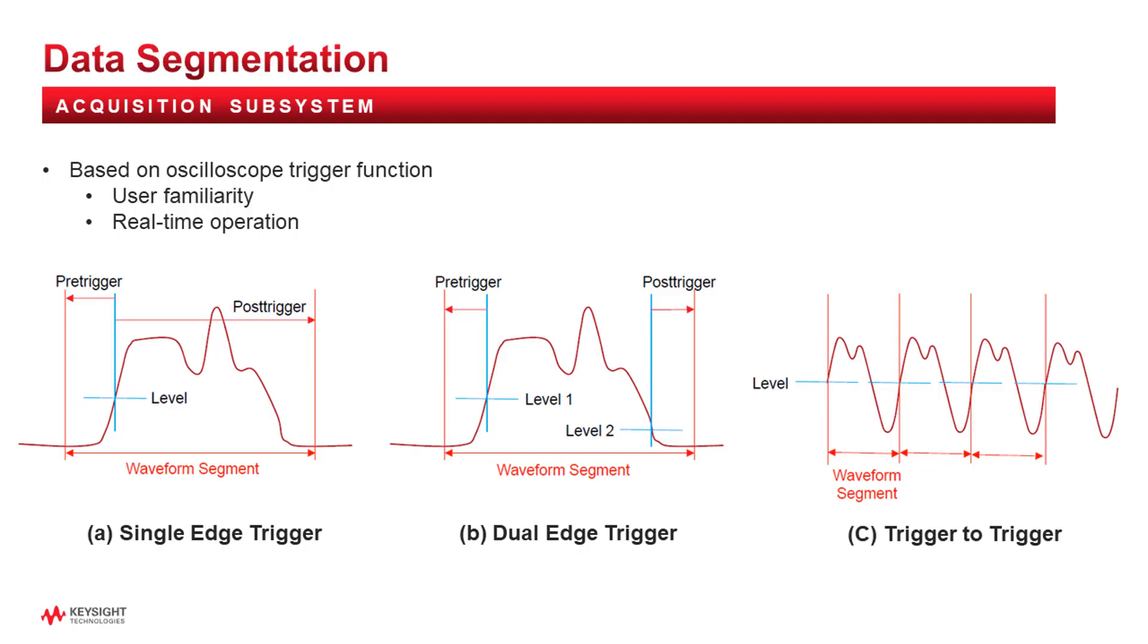Waveform segments are defined using various combinations of the trigger functions. The Anomalous Waveform Analytics feature can extract and classify waveforms concurrently as it is recording live long duration measurement data.